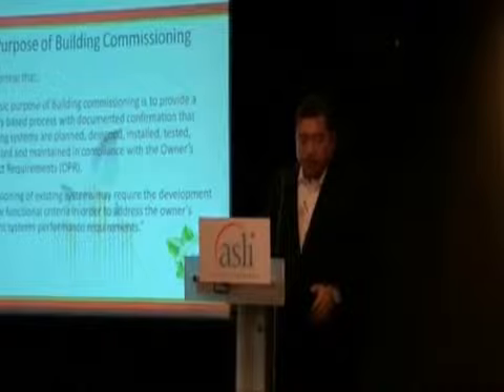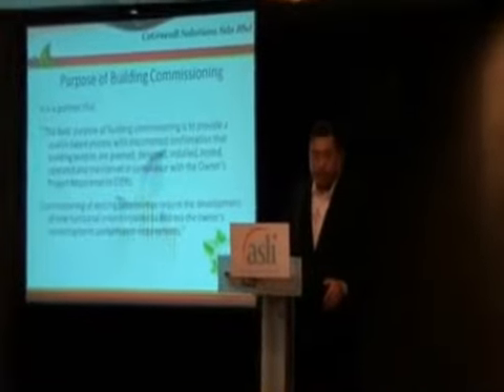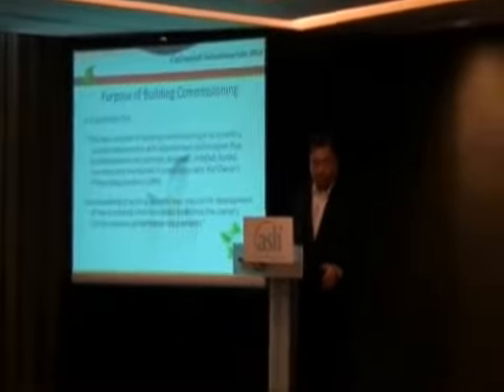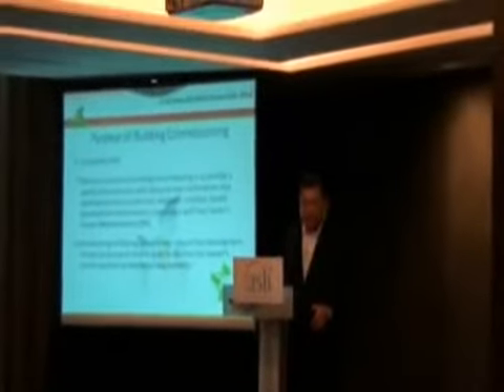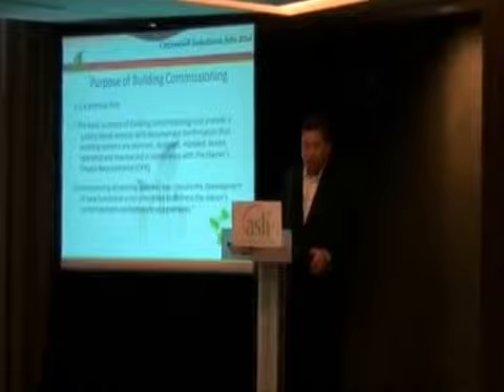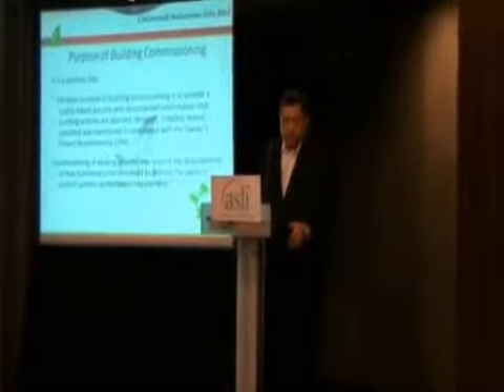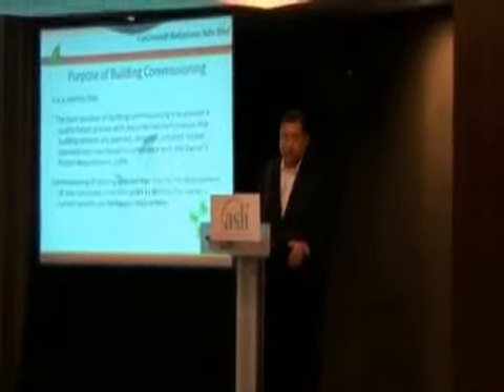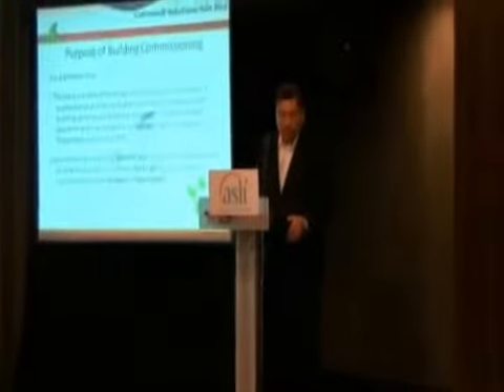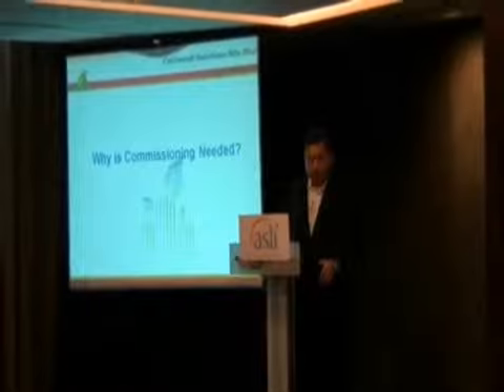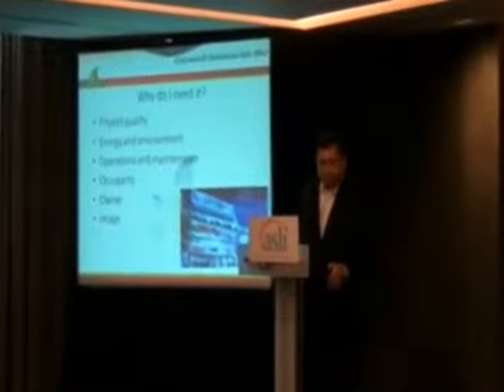The basic purpose of building commissioning is to provide a quality-based process with documented confirmation that building systems are planned, designed, installed, tested, operated, and maintained in compliance with the OPR. Commissioning of an existing system may require development of new functional test criteria to address the owner's current system performance requirements.